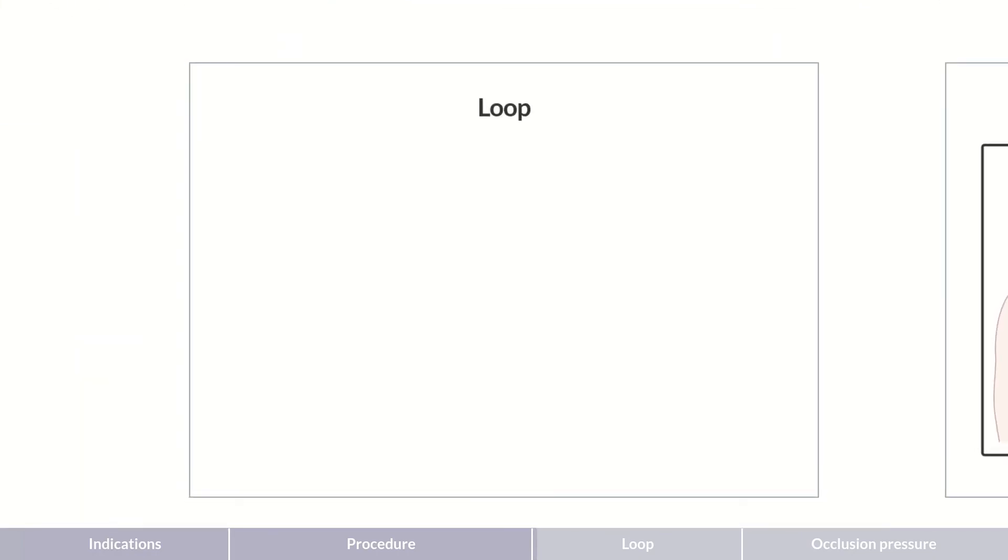The displaced volume of air and the airflow can be depicted graphically during measurement. As a reminder, airflow is recorded with the mouthpiece that occurs simultaneously with cabin pressure measurement. Airflow is plotted on the y-axis of the diagram and the displaced volume on the x-axis.